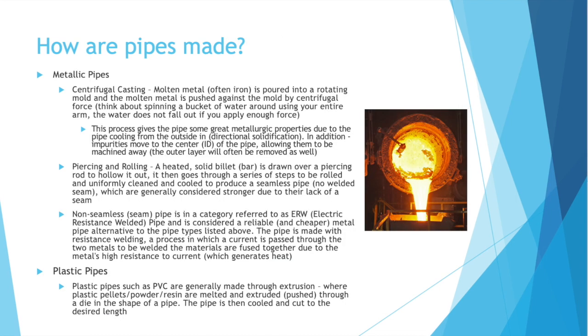How are pipes made? For metallic pipes, you have centrifugal casting. Molten metal, often iron, is poured into a rotating mold, and the molten metal is pushed against the mold by centrifugal force — similar to spinning a bucket of water around using your entire arm. What's great about centrifugal casting is that it gives the pipe excellent metallurgical properties due to the pipe cooling from the outside in, known as directional solidification. In addition, impurities move to the center — the ID of the pipe — allowing them to be machined away, leaving pipe with very good metallurgical properties and few impurities.